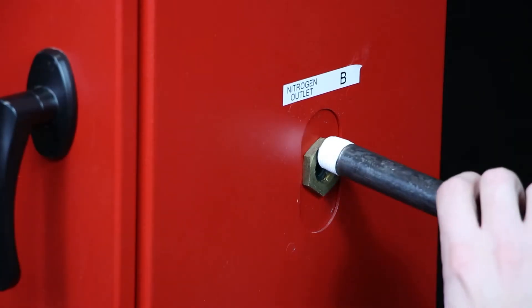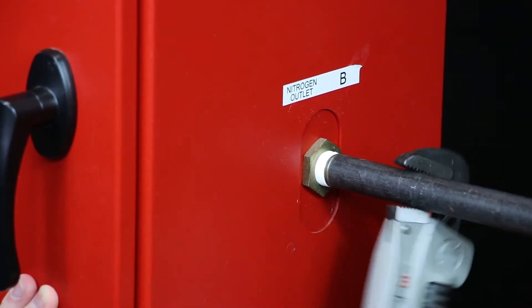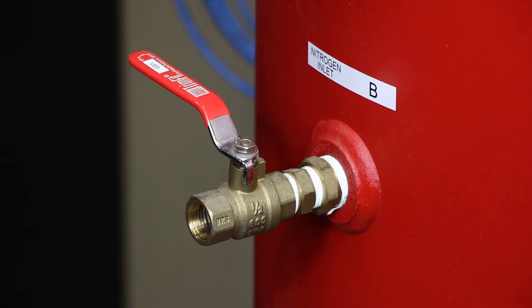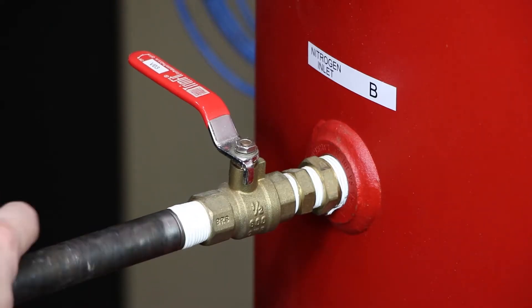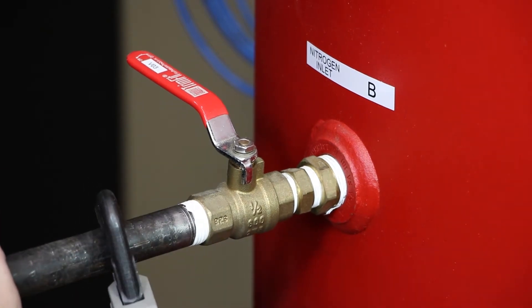Install half-inch NPT piping from the half-inch female NPT outlet labeled nitrogen outlet connection B on the nitrogen cabinet to the half-inch female NPT inlet valve labeled nitrogen inlet B on the nitrogen storage tank.